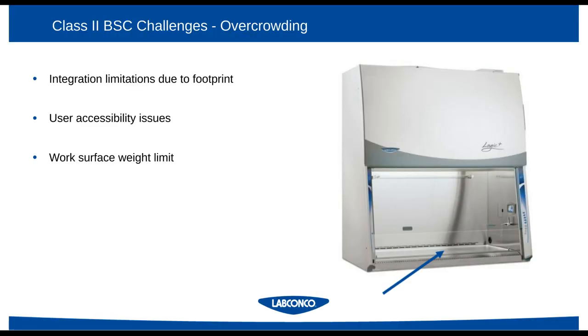Also, a key thing to consider is the work surface weight limit. On a traditional biosafety cabinet listed to NSF 49, the work surface will be tested to a 50-pound weight load. Some manufacturers allow for more weight. Labconco does as well, but it's important to address the amount of weight, where it's going to be positioned inside the biosafety cabinet, and how the robot or other automated system is going to be behaving and redistributing weight as it operates. So checking with the manufacturer can help out with those questions.